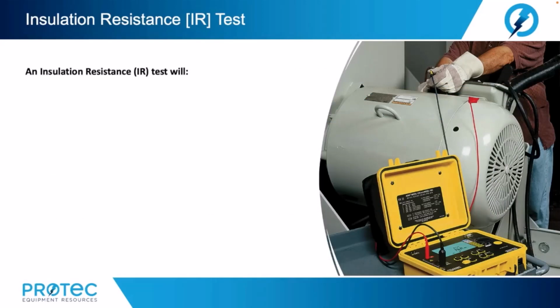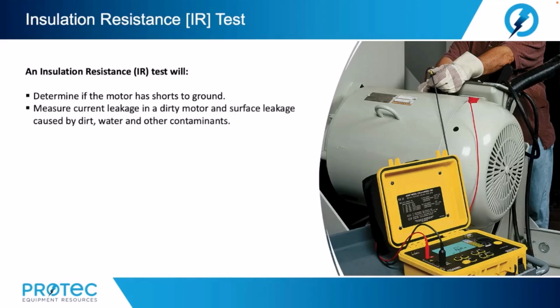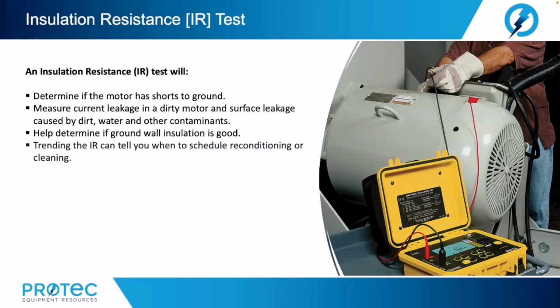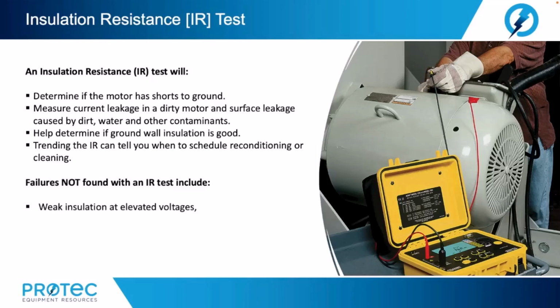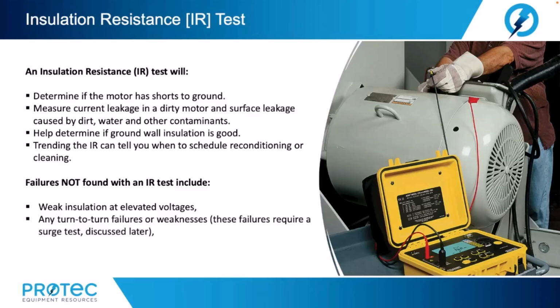So, an insulation resistance test will determine if the motor has shorts to ground, measure current leakage in a dirty motor and surface leakage caused by dirt, water, and other contaminants. It helps determine if ground wall insulation is good. And trending the insulation resistance can tell you when to schedule reconditioning or cleaning. Now, failures that are not found with an insulation resistance test would include weak insulation at elevated voltages, any turn-to-turn failures or weaknesses. Now, these failures require surge tests, which we're going to discuss later. Connection problems, open phase, phase-to-phase fault.